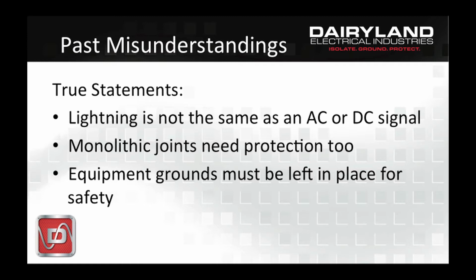And last topic discussed in the previous presentation would be that equipment grounds have to be left in place for safety. You cannot sever an equipment ground just because it's a nuisance for your cathodic protection system. It really must be left in place. Instead, there are decouplers that are UL listed to be placed in series in grounds to solve these kinds of problems.